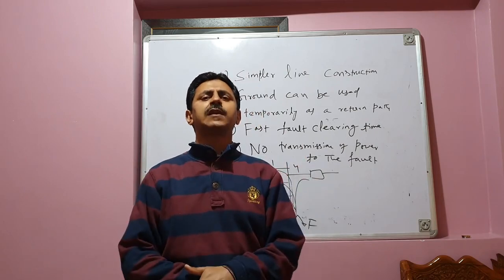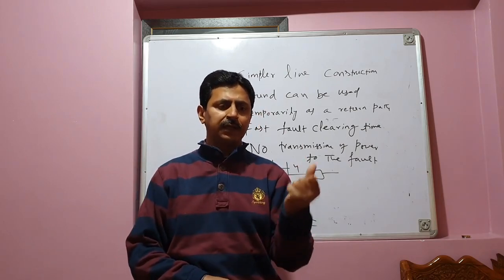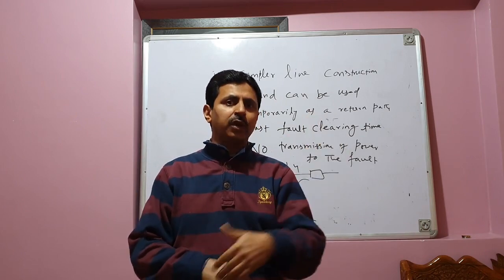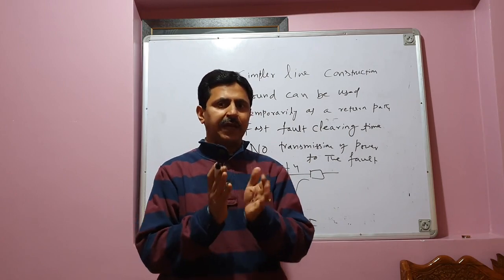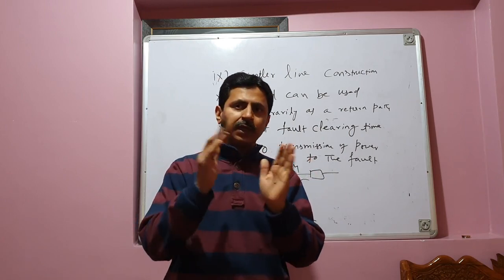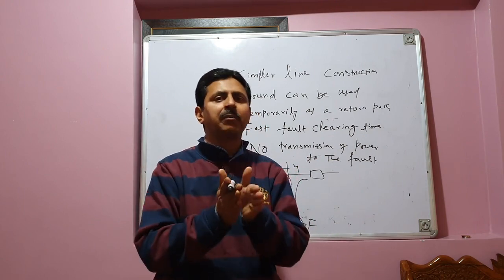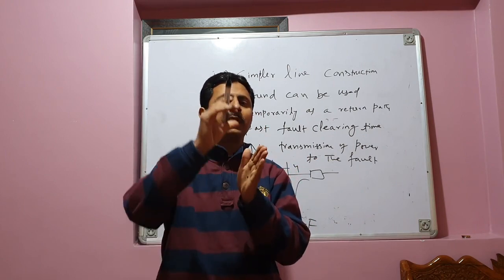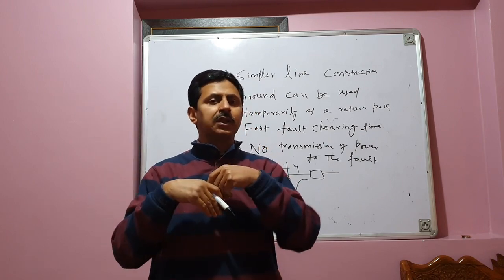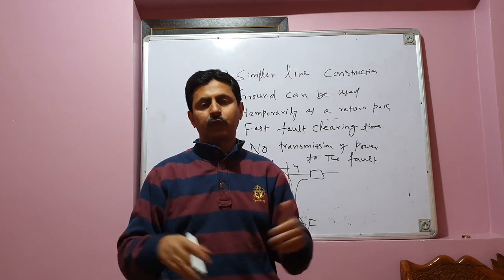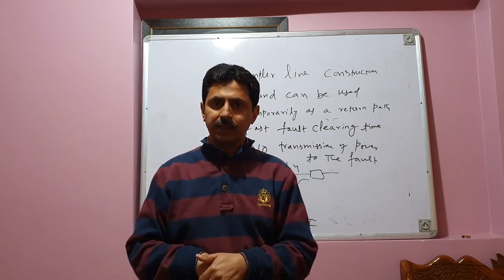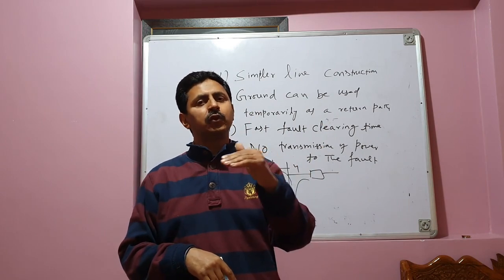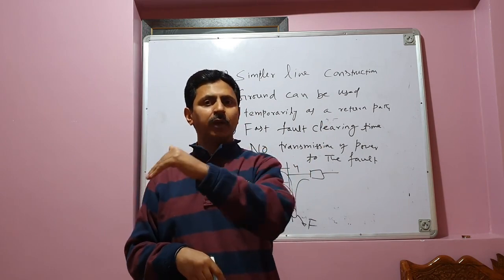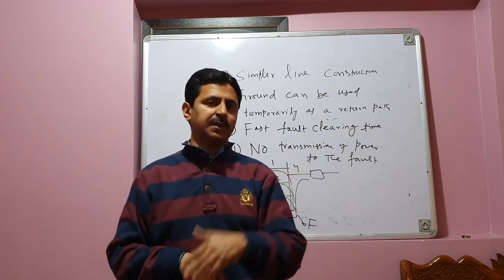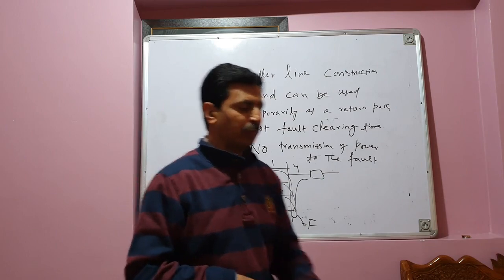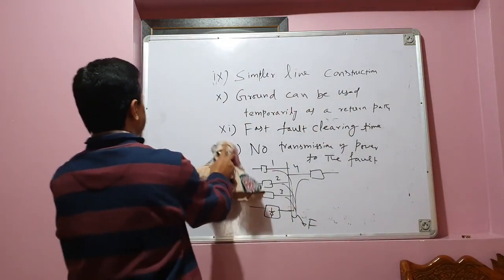because the HVDC transmission system is electronically controlled. Whenever the controller senses that the magnitude of current has increased, it takes care of that. It adjusts the firing angle or delay angle of the converters at the converting stations, and it limits the magnitude of fault current. And in the worst case, it may make alpha equal to 180 degrees, for which the converter output becomes 0, and therefore there is no transmission of power to the point of fault. The HVDC transmission line does not contribute anything to the power at the point of fault, whereas AC transmission lines, for some time, may contribute to the flow of power to the point of fault. This is another advantage of HVDC transmission over AC transmission.